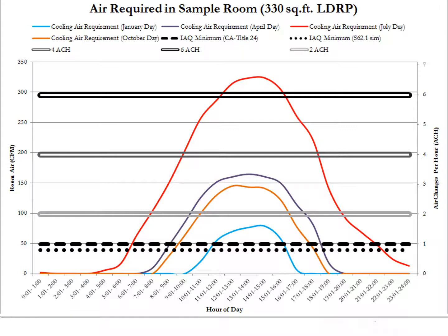The red line is a summer day, and the blue line is a winter day, and the horizontal lines are the code and standard lines. For hygiene level ventilation, 15 CFM per person, or the alternate two-variable approach—those are the lower, dotted lines down at the bottom of the chart.